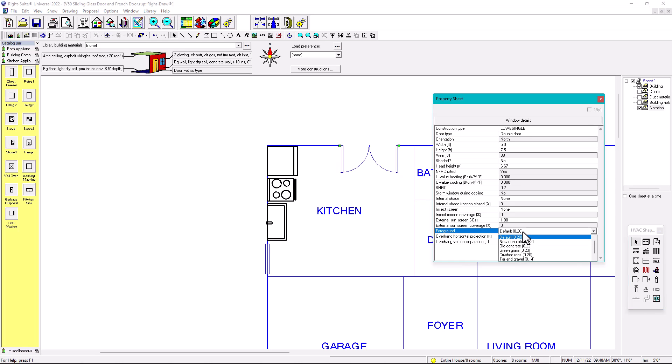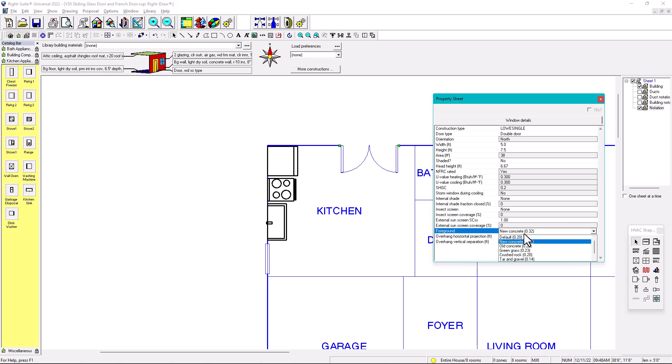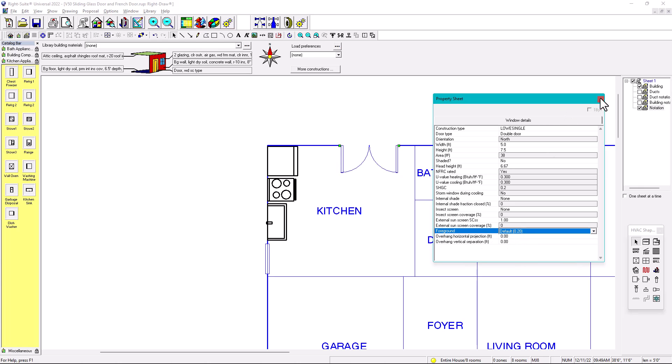If you want to take a very conservative approach, like if you want to oversize a little bit your system, for example, you get a two ton unit. If you change this to 0.32, you might have a 2.2 ton unit. So you are oversizing, in other words, somehow to be very, to be safer. But I usually leave it in default 0.20. This is the Albedo foreground. And we also made a video of what is Albedo or foreground reflectance.